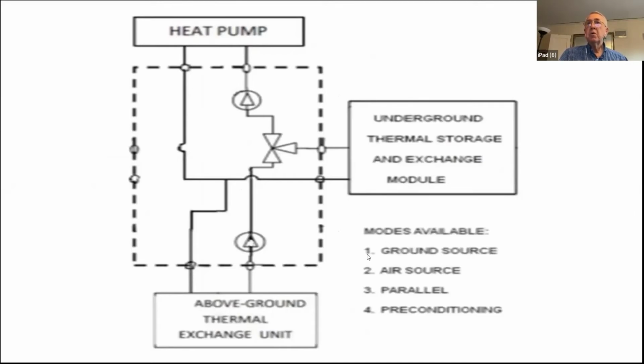Now, there are still four different modes operable for this system. The ground source mode, where we use only the right-hand block flowing through the valve this way. The air source mode, where we only have flow going up this way and back down through the above ground unit. Of course, that could be solar thermal or air to liquid exchange or whatever. We also have the parallel mode, where if the flow rate in this top pump is twice the flow rate of what's in the bottom pump, then we will have an equal flow from the right-hand block and from the above ground block here. And there's also a preconditioning mode.